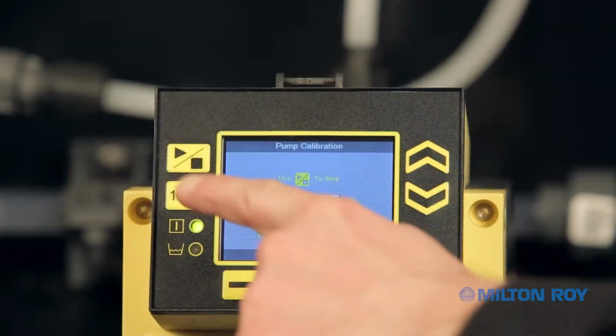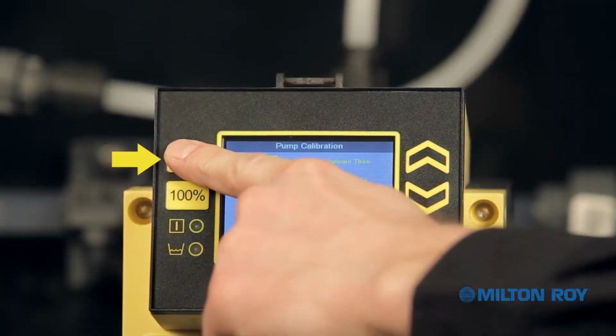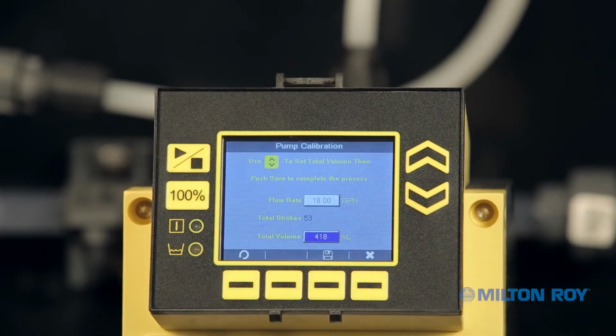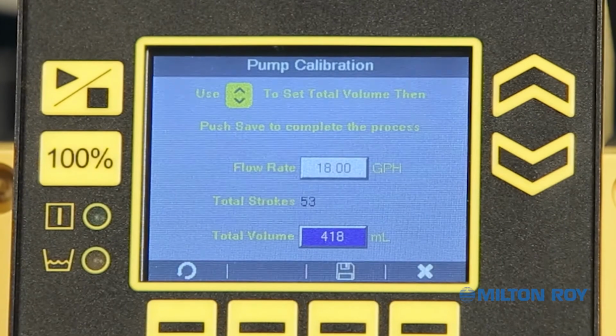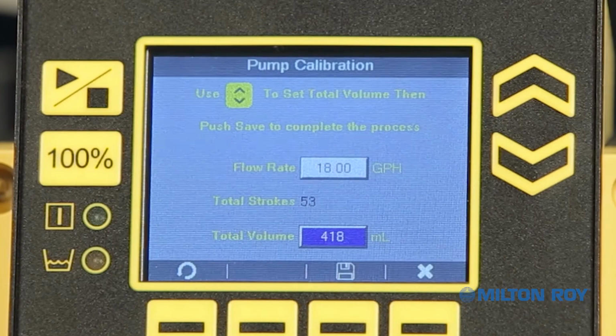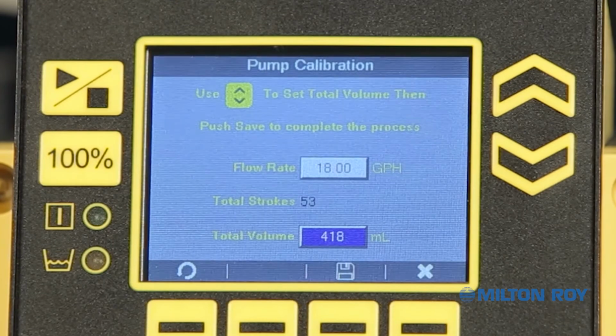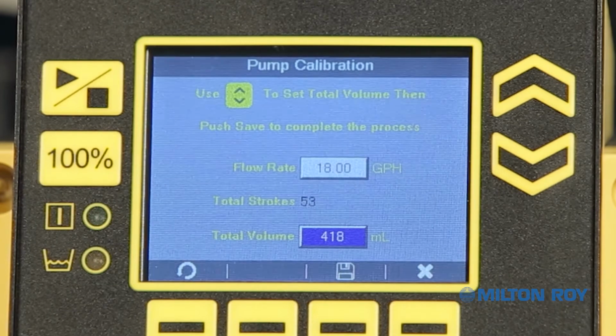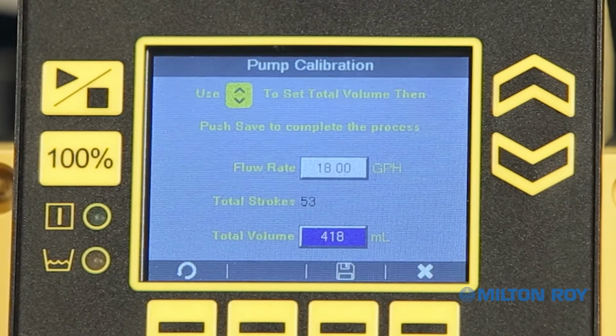Once the fluid level approaches the bottom of the scale on the column, stop the pump before the level goes below the scale. Note, pumping a complete cylinder allows for a more accurate calibration. With the pump stopped, you can now review the calibration settings. In this example, we will use the flow rate identified on our screen of 18 gallons per hour. The total stroke count is 53, with a total volume of 418 milliliters.